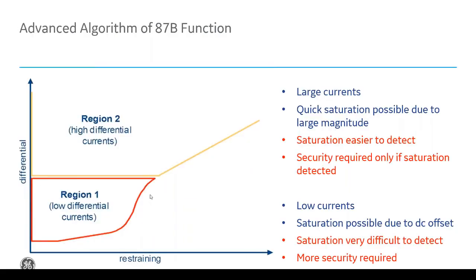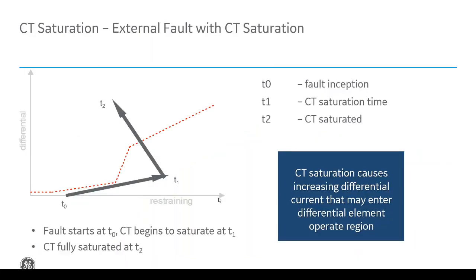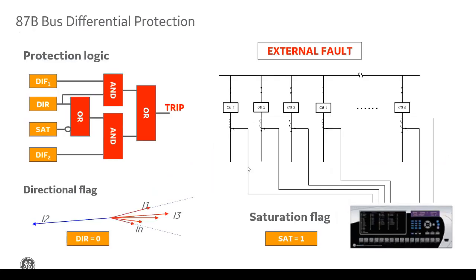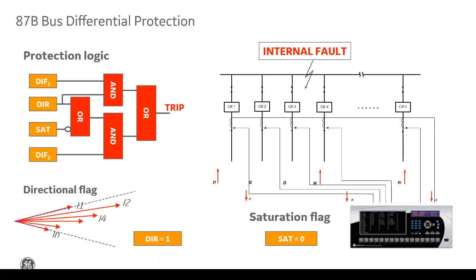But if I have a high level fault, if it's internal, meaning there's no CT saturation, it does not go to T1 anymore, it goes right from T0 to T2. So I know that that's an internal fault and I don't need to look at that directional flag. However, if there is an external fault with CT saturation, I see that it goes from T0 to T1 to T2, then I say, hey, saturation is detected, and I need to look additionally at the directional flag. So I still have fast tripping, but I have security for external faults.